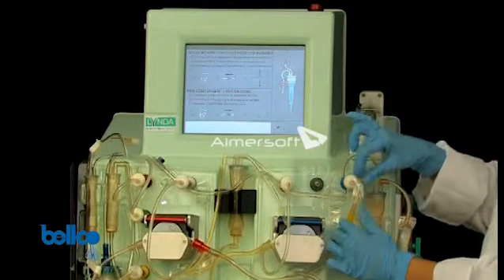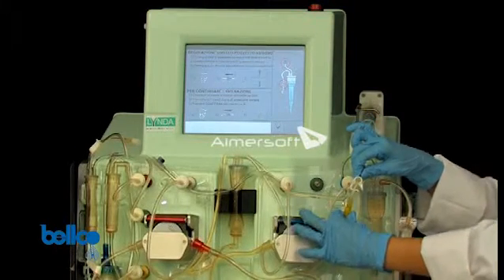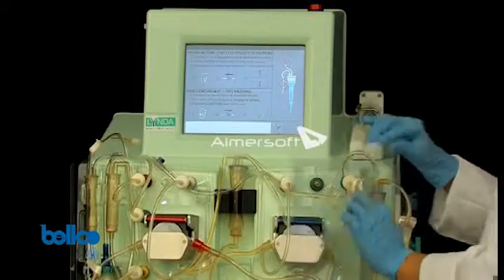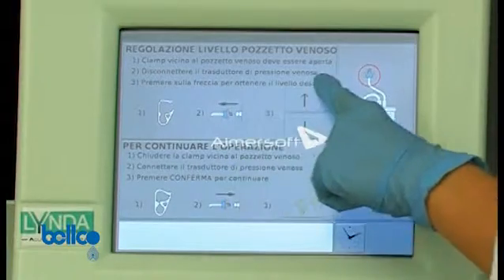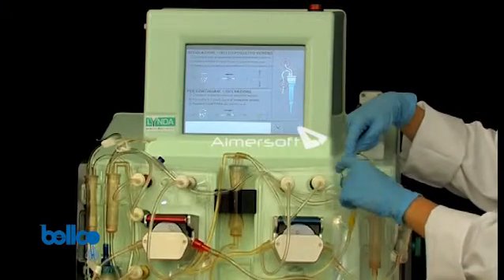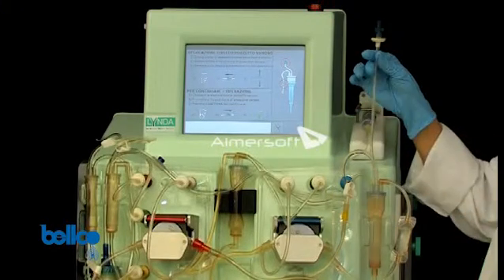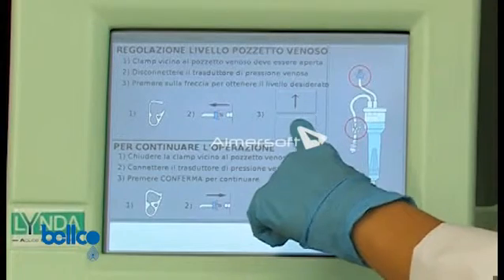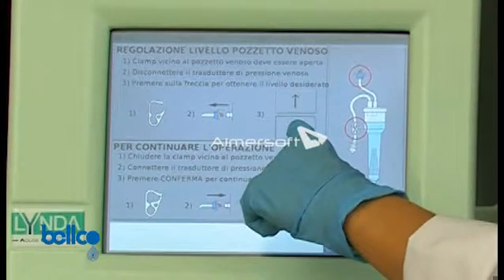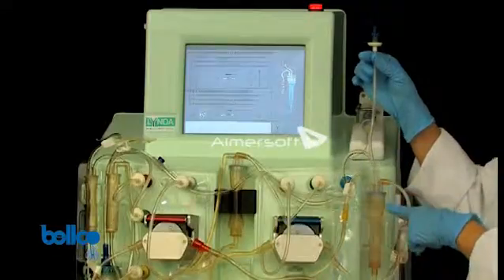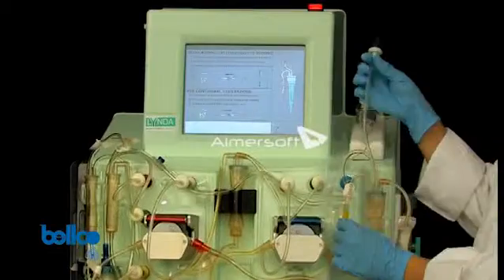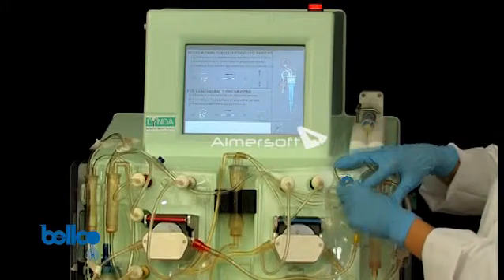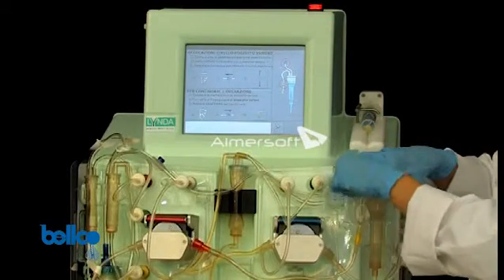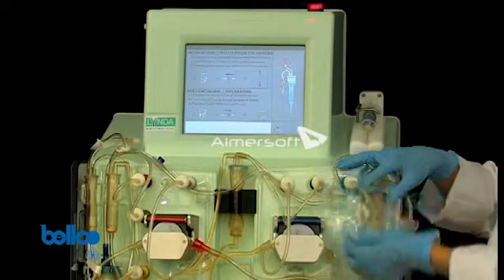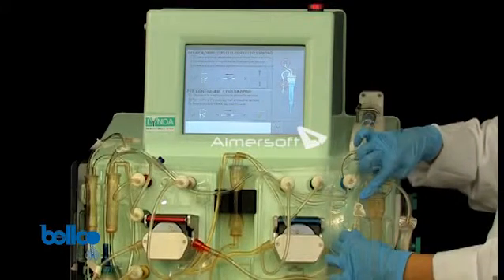At the end of priming, you need to adjust the venous chamber. The clamp near the venous drip chamber must be open as shown. Disconnect the venous pressure transducer and adjust the levels with the arrows on the screen. When done, reconnect the venous pressure transducer to the machine and close the clamp near the drip chamber. This clamp must stay closed throughout the treatment.